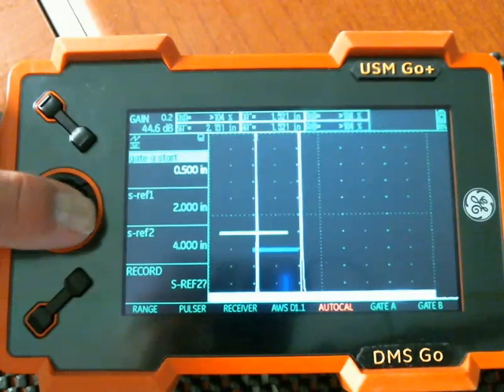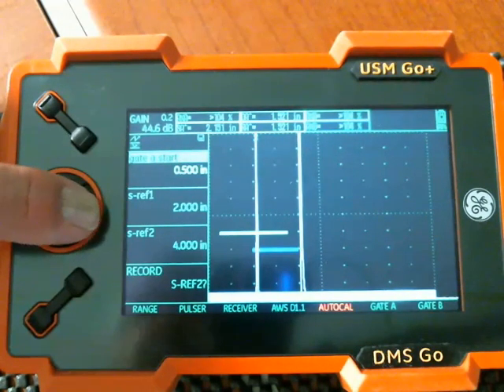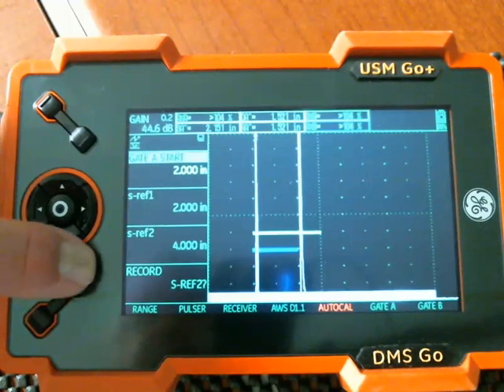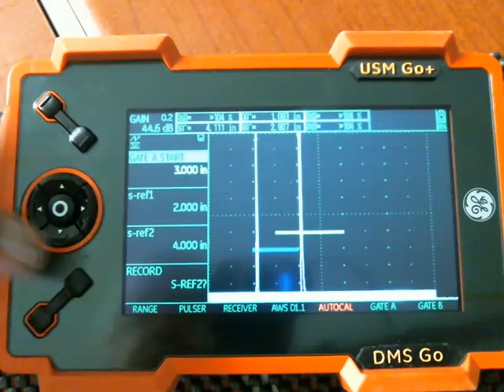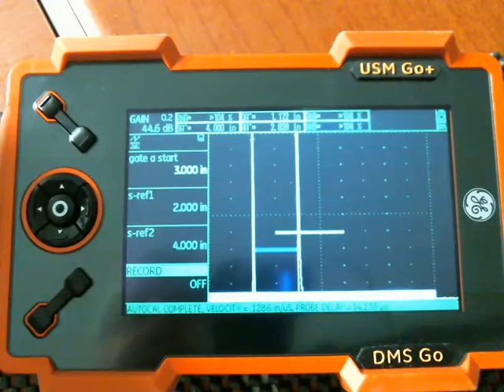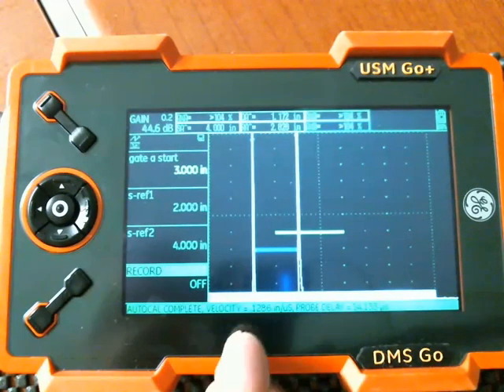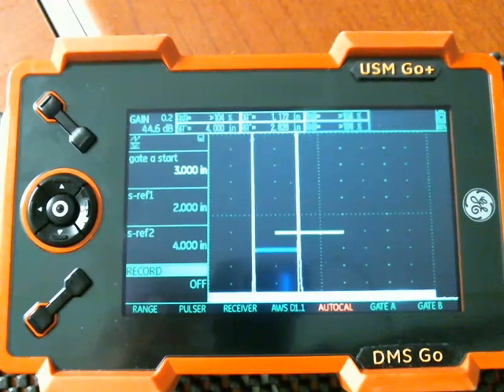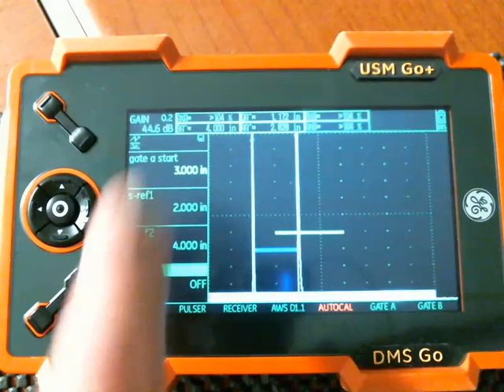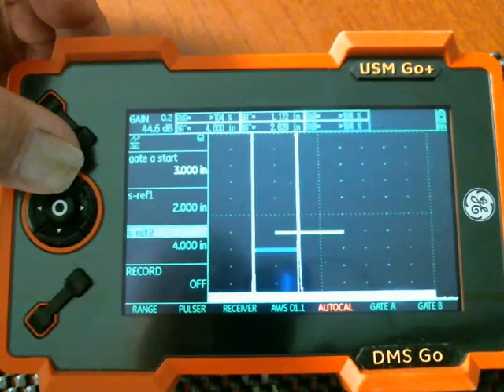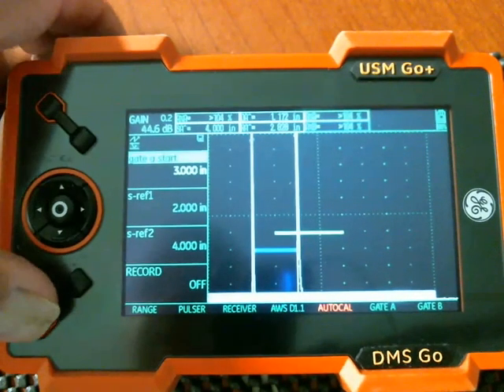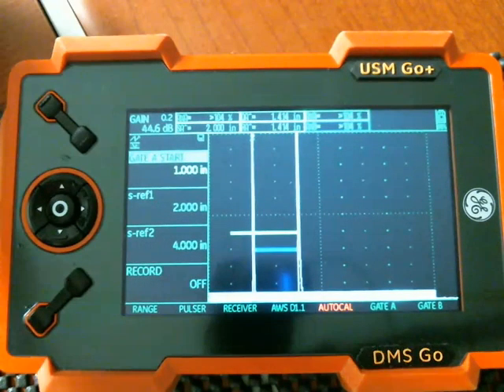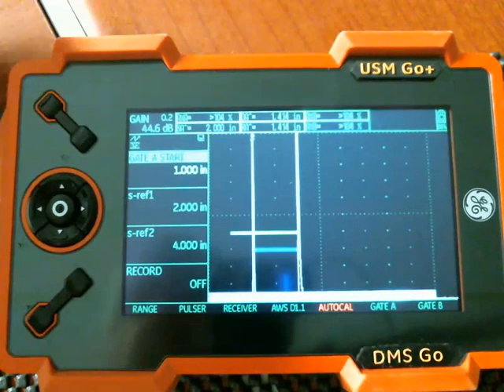Now it says set up over ref2. So I'm going to increase my gate A delay to move the A gate out onto the four inch echo. And down here and complete the calibration process. Auto Cal complete velocity 0.1286. And it's at the range as well. So now you notice the distance in gate A is four inches. If I move my gate A start back to catch the other echo, two inches. So at this point, we're all set up for distances.